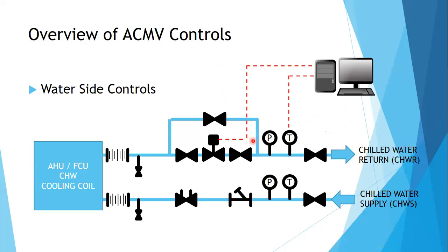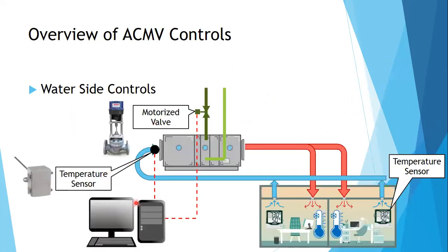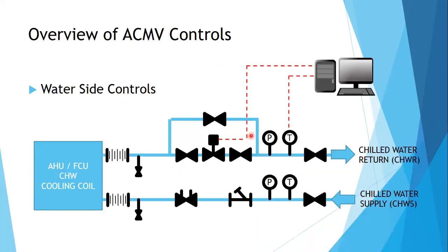Okay, so how is it being controlled? So now the temperature here. Previously we said we're controlling this motorized valve based on the temperature sensor of your return air duct or the temperature condition of your room. Just like the cooling tower, there are also two options. Either you monitor the air temperature or you monitor the water temperature. It will also give you the same effect. By monitoring the water temperature, you'll be able to determine if the motorized valve needs to be closed or open or partially closed or partially open according to your set point. Again, your set point is being monitored by your temperature sensor, temperature gauge. The signal is being sent to your BMS or your PLC where your control logic is located. And those signals are being analyzed so that they can send the appropriate signal and appropriate action to your motorized valve.